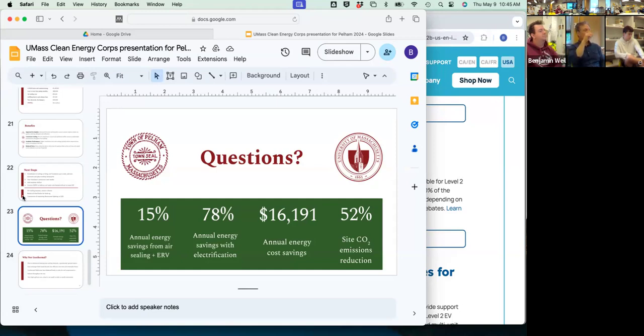And he tested a bunch of these things, and I'm also trying to convert now to Fahrenheit. Basically, you could be 4 degrees below dew point and you would start to get condensation, but you didn't get droplets that actually coalesced and formed into droplets that drop. So there's a certain amount of buffer in that, which allows hydronic systems, HVAC systems in general, but hydronic systems in particular, are very slow.